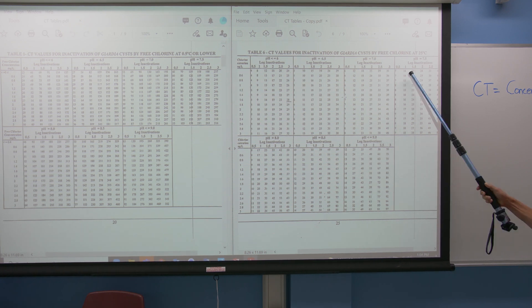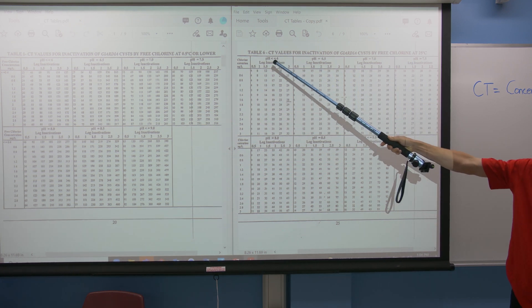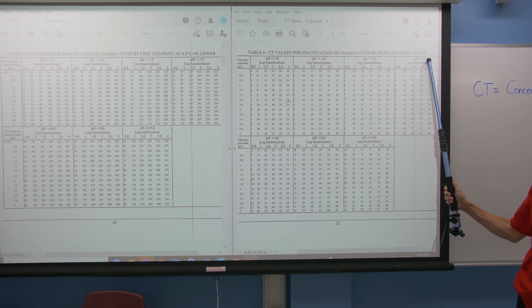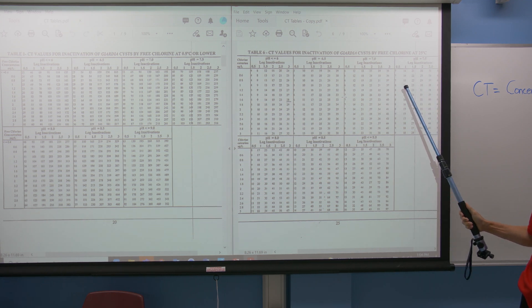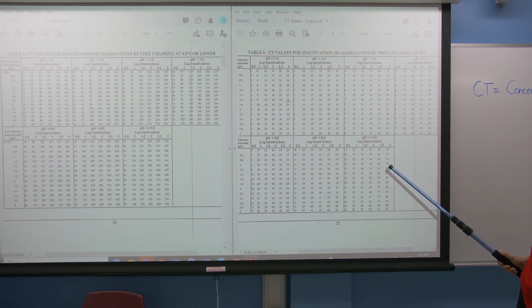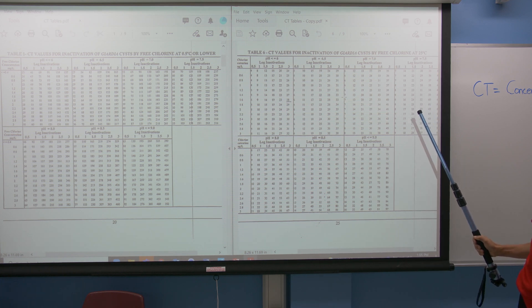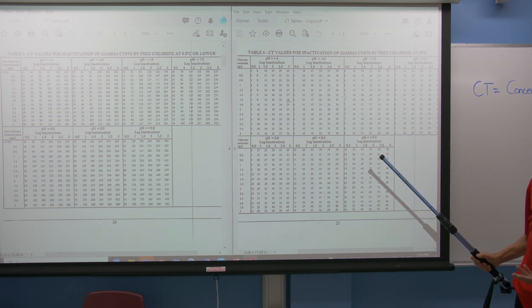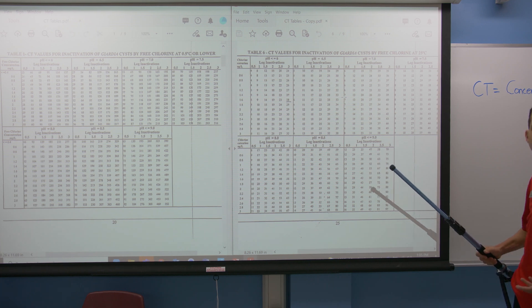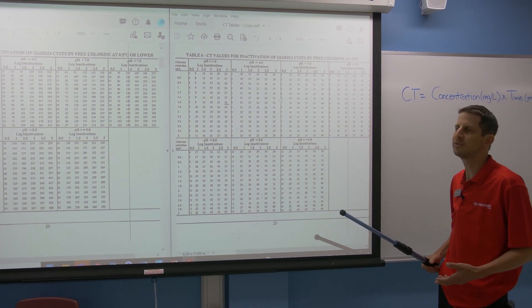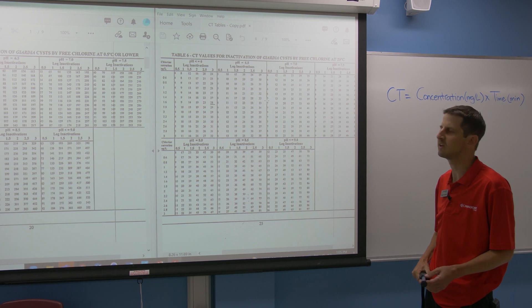We can compare that over to Table 6, looking at pH 9, 2-log removal, concentration of 2, and the CT value is 59 — much lower. The difference between Table 1 and Table 6 is that Table 6 is at 25 degrees — much warmer water — and you can see a much lower CT value. So higher temperature means more effective disinfection, and that makes sense because bacteria and chemicals are moving faster at higher temperatures, so inactivation is happening faster.